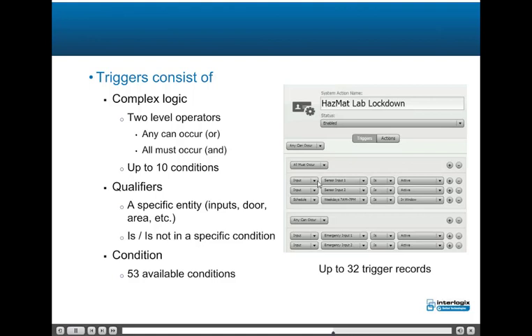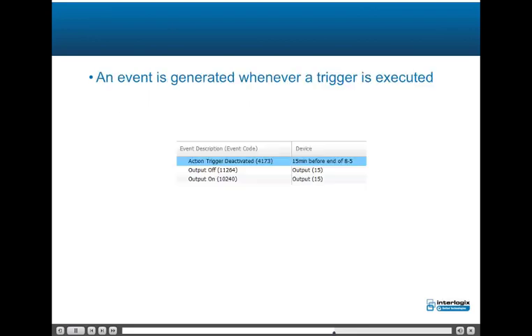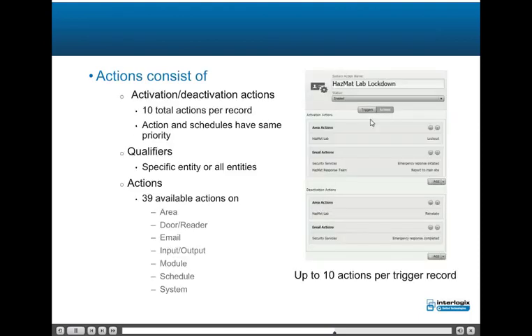An event is generated whenever a trigger is executed, informing the operator the action took place. Actions consist of activation and deactivation actions; the system supports up to 10 total actions per record. Actions and schedules have the same priority in the system when executing. Qualifiers include a specific entity or all entities, with 39 available actions on areas, door/reader, email, input/output, module, schedule, credential, and system. Action triggers may be created based on a specific credential being used, and the following actions can be set for various access granted and access denied events. To configure an action trigger for a credential, choose credential as the trigger, then choose the specific credential ID from the drop-down list, then choose the type of credential event to use as the trigger.